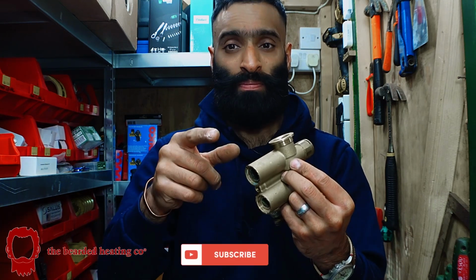When the boiler fires up, even this boiler will give you overheat errors if that gauze filter is blocked. Always check your inline filters. Every boiler will have one on the flow as a minimum, and as an additional precaution, it may also be on the return coming back from the heating circuit before it hits the boiler.